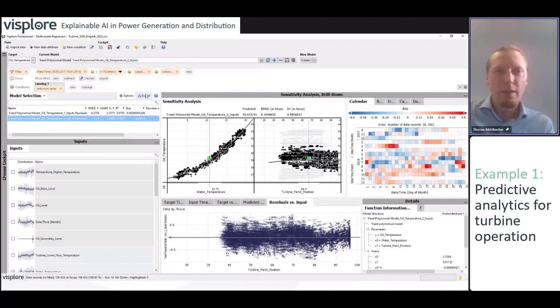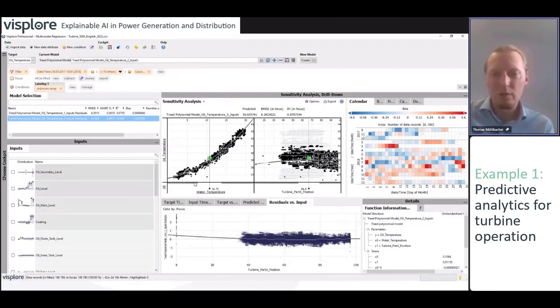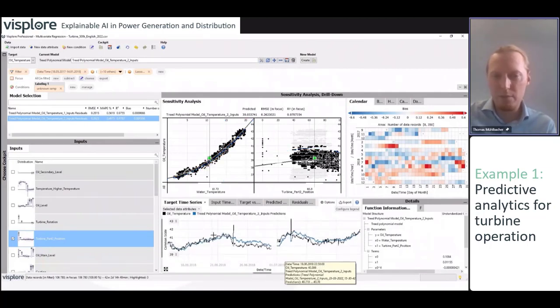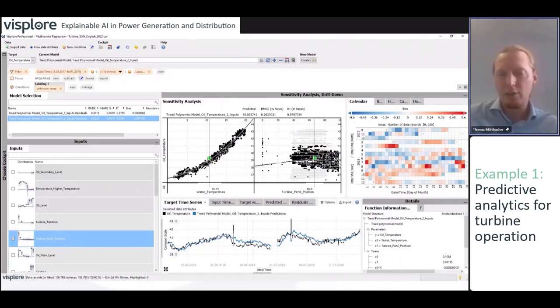Maybe also just one thing, we have these unknown ramps here that we had excluded. So maybe let's include them again in the visualization and look at the actual prediction that we have made here as a time series. And you see here now, our prediction time series is in blue and the measured values are in black. And you would nicely see that these unknown ramps that we have in here are quite strong deviations from our expected modeled behavior. And by defining a threshold here, for example, like 1 degree or a bit more, these would actually be able to be recognized for condition-based monitoring, for example.